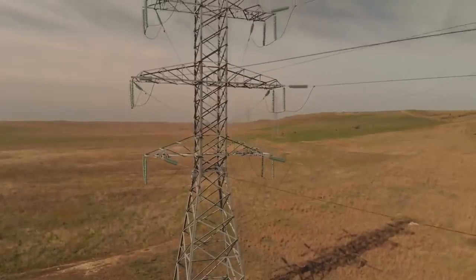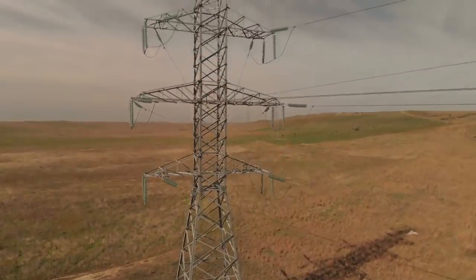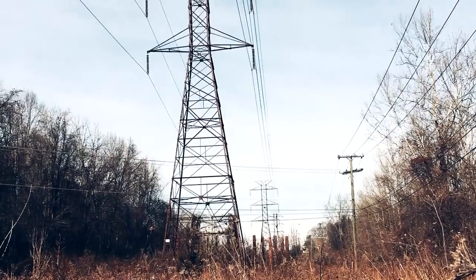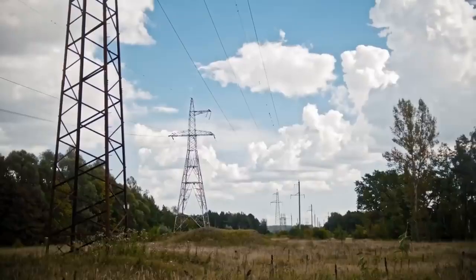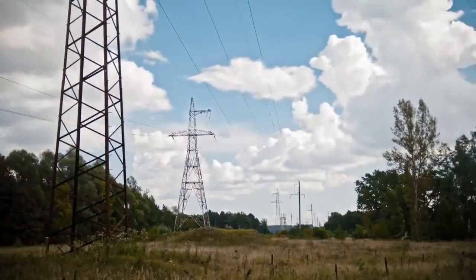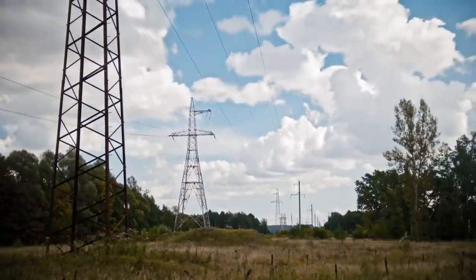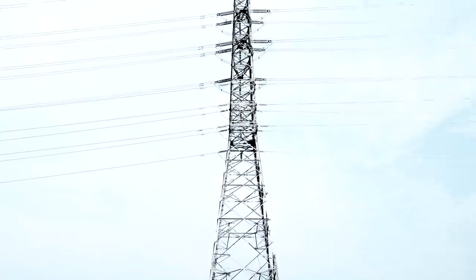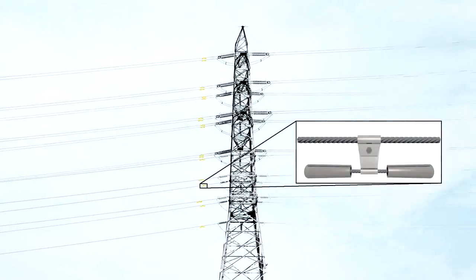These lines can get really hot and sag during peak electricity demands, which can cause problems if tree branches are too close. Wind can also affect the conductors, causing oscillations that lead to damage or failure of the material. You'll often see these small devices called Stockbridge dampers to absorb some of that wind energy.